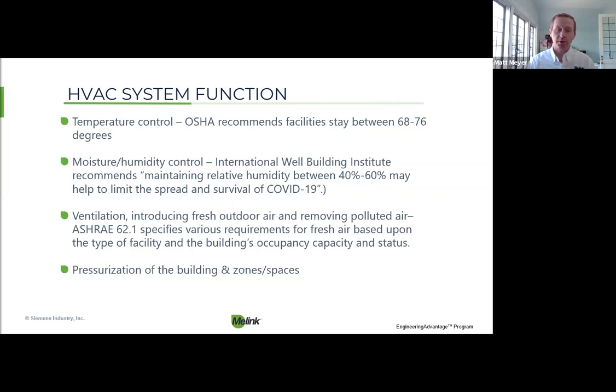So it is very important that you consult this guide, the ASHRAE guide, to understand how your facility should be set up, or what the recommendations are for your facility to be set up. And then next is pressurization of the building. I touched on that on the previous slide. You want your building to be at a slightly positive. You don't want it to be at an overly positive state where you're bringing in lots of outside air and then just blowing your doors open. That's not what you want either, because that doesn't leave everybody in a good comfort space. But there's a happy medium that you find there.